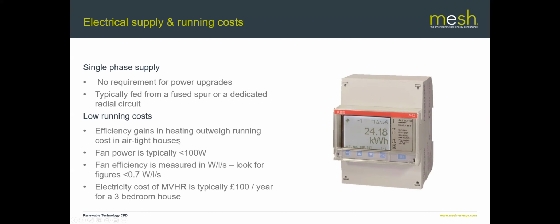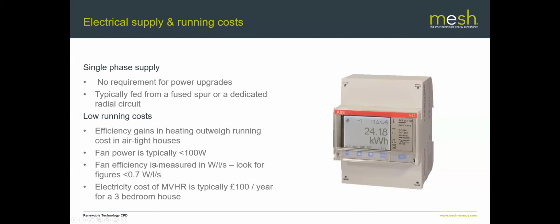As that graph that we showed earlier, efficiency gains from the heating system will outweigh the running costs in most relatively airtight modern houses. The fan efficiency, which is something to look for when you're specifying an MVHR unit, is given as a specific fan power, and that is in watts per litre per second, and you should be looking for a value of around 0.7 watts per litre per second.